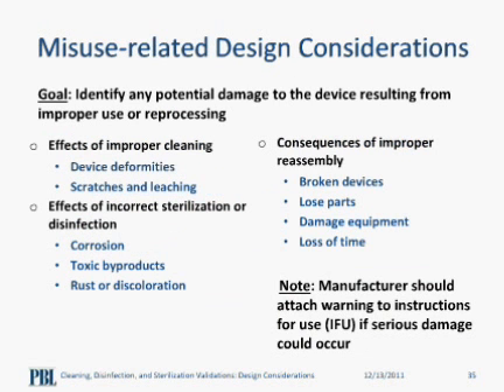So why do we have to consider misuse-related designs in manufacturing medical devices? Because it does not only affect the functionality of the device, but may also impose danger to users. It is important to anticipate and determine what harmful effect can happen if any incorrect cleaning, disinfection, or sterilization process is used. With this in mind, we can include a margin of safety just in case it happens.